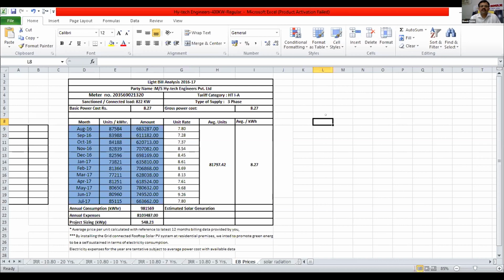In commercial HT connections, normally we use solar only in daytime, between 6 a.m. to 6 p.m., so we need to understand the user's exact consumption pattern. On any HT bill, we understand how much consumption they do in a month, and accordingly, as I explained, the insolation available at that location, you directly divide by the unit rate. So you come to know the project sizing of solar for that particular user and location.